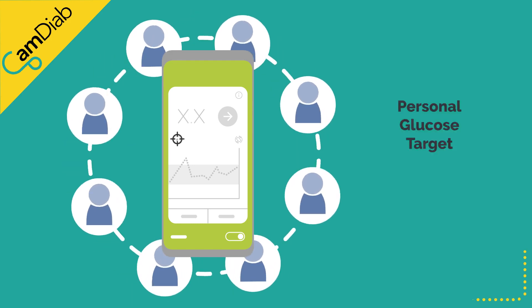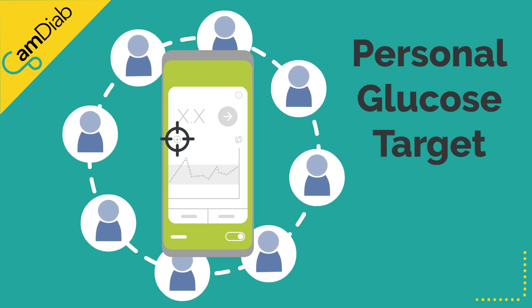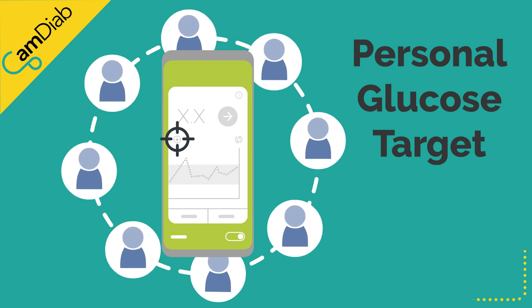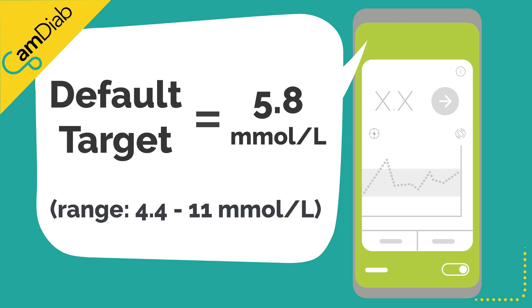MyLifeCam APS FX's algorithm has a customizable personal glucose target that it aims to achieve when auto mode is running. The default target is 5.8 millimoles per liter. You are able to set this target anywhere between 4.4 and 11 millimoles per liter across the 24 hours of the day.